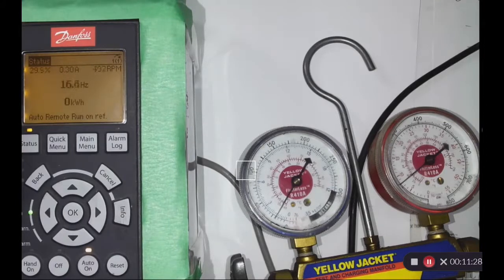And obviously the command for calling is, I have it as a digital switch, but obviously you'd want a command, say, from a relay, from a thermostat, calling for cooling, calling for heating, whatever the case may be, and then it's running on the reference now, which is almost the minimum that it would run at. I'll just bleed it all off. There you go. That's the lowest it's going to go down to. And again, you can get rid of that by changing that value to the minimum. Okay? And I'll just take my switch, open it up, and now you can see it's quit and it's on auto remote. It's on standby, waiting for a command.